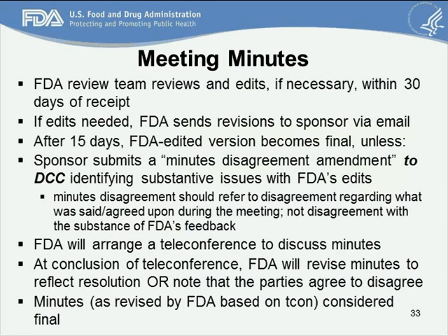The minutes disagreement should refer to disagreement regarding what was said and agreed upon during the meeting, not disagreement with the feedback that was provided. If a meeting minutes disagreement amendment is submitted, FDA will arrange a teleconference to discuss those minutes, and at the conclusion of the teleconference, FDA will either revise the minutes to reflect resolution or note that the parties agree to disagree. The minutes that were revised by FDA based on the telecon are considered final.